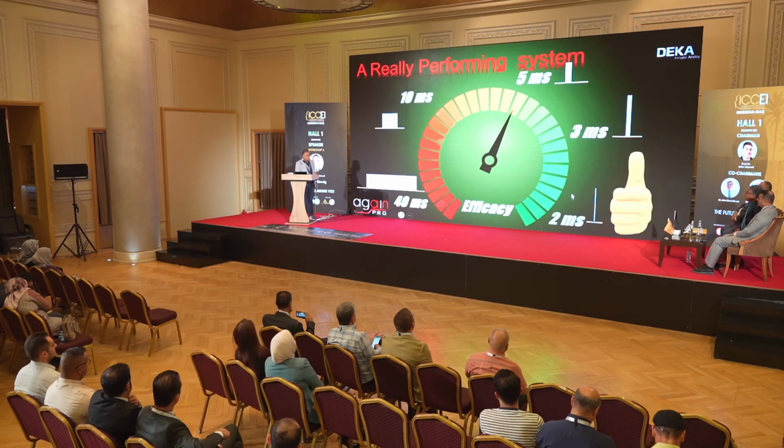When I told you about fluence, we need to increase it when the hair follicle becomes finer or thinner. And vice versa with the duration. You need to decrease it while the hair follicle is becoming finer. Of course, sometimes we need to go down to 2 milliseconds.